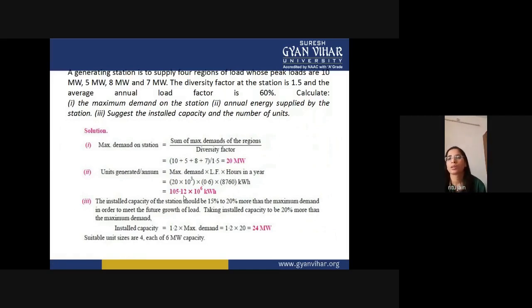Now let's come to the next point, the installed capacity of the station and what must be the number of units. The installed capacity of a station should be 15% to 20% more than its maximum demand, in order to meet the future growth of the load. So taking installed capacity to be 20% more than the maximum demand, the installed capacity is equal to 1.2 into maximum demand, so you will get 24 megawatt. So the installed capacity of the generating station is 24 megawatt, and the maximum demand is 20 megawatt. So suitable unit sizes are 4 units, each of 6 megawatt capacity.